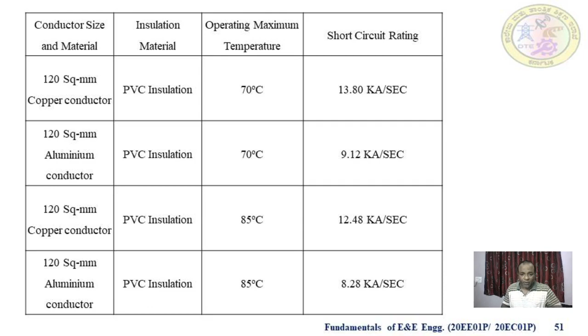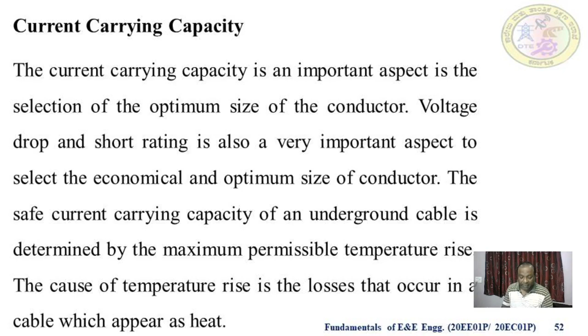Current carrying capacity is also important for cables. The current carrying capacity is an important aspect in the selection of the optimum size of the conductor. Voltage drop and short circuit rating are also very important aspects to select an economical and optimum size of the conductor. The safe current carrying capacity of an underground cable is determined by the maximum permissible temperature rise. The cause of temperature rise is the losses that occur in the cable, which appear as heat.